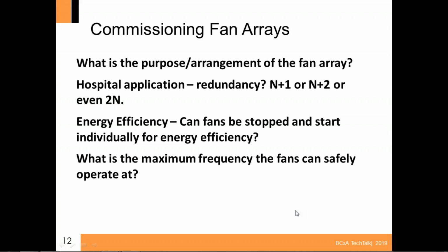Yeah, I've never seen them blow the overload coming back, but the point is a very good question. Every fan wall that I've ever worked on, we've always had a means to shut off the flow coming back through it. We've done different things like looking at differential pressure across the fan itself between the plenums, but that doesn't seem to work very well. But usually what we'll do is use a CT on each one of the overloads. We'll have a CT for each individual fan, and then when that fan fails, we have a motorized damper with a low leak damper on it, and we shut that one off. We do not typically like to see barometric type at all.